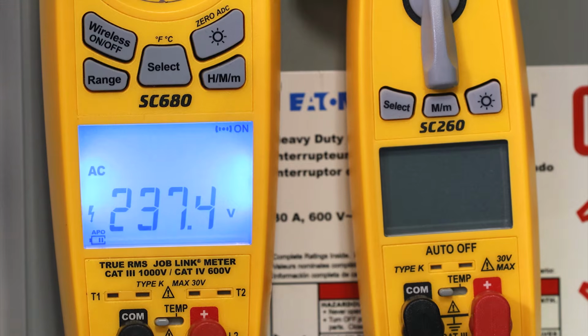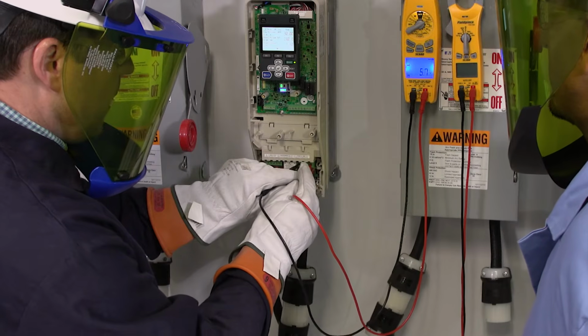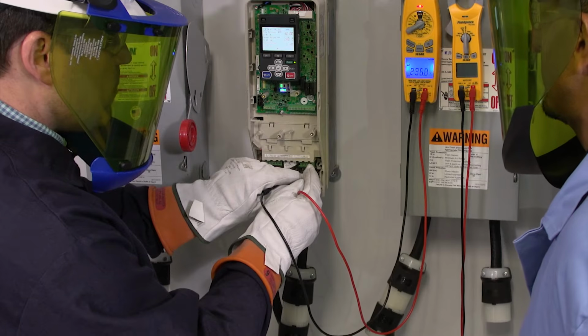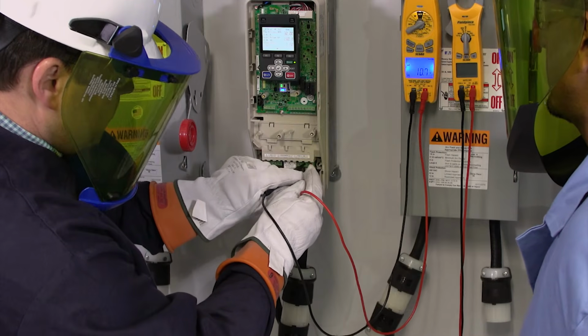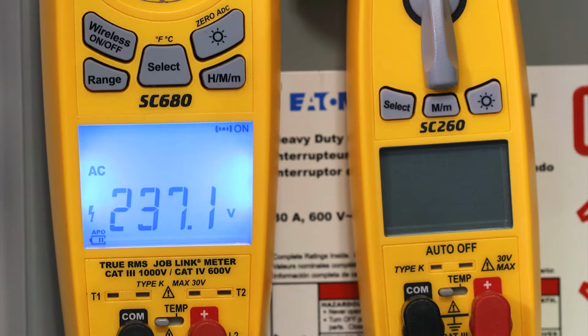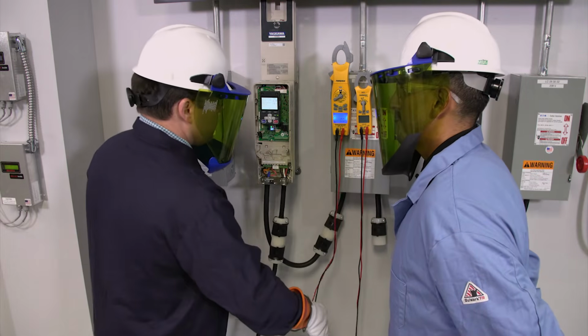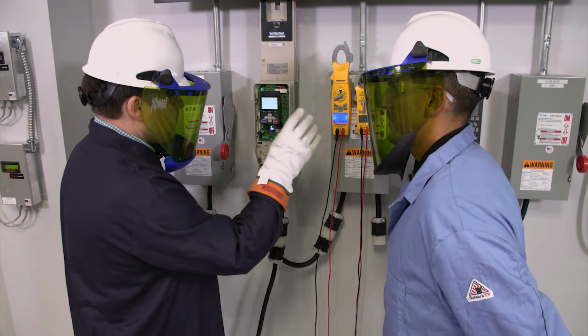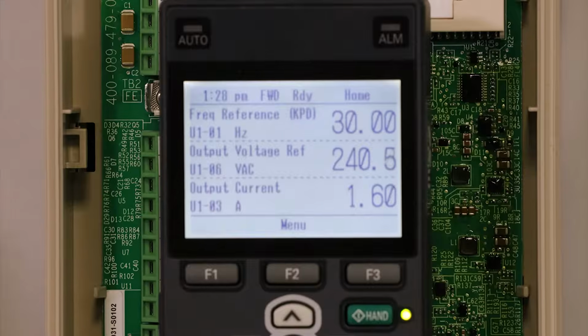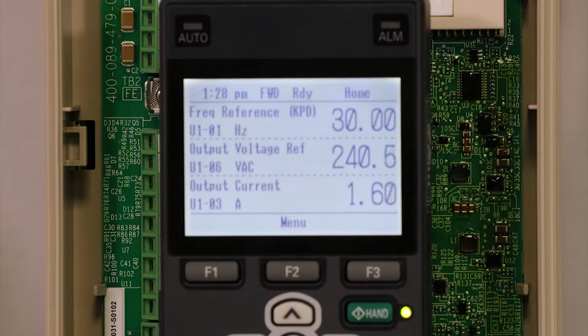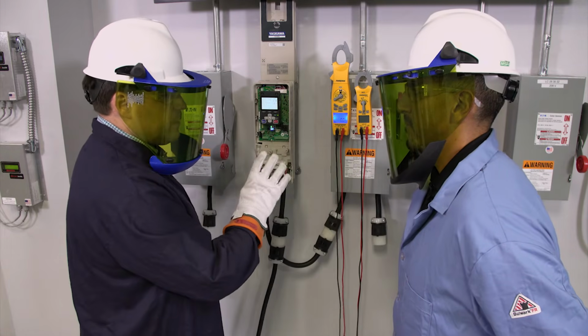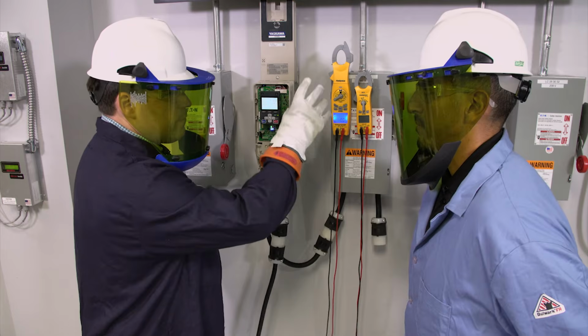You can see here we're at 237 volts, which is much less. 237 volts. 237 volts. Quite a bit of difference between those two readings. We know the filtered measurement is a lot closer to reality because the VFD's output voltage is approximately 240 volts. This proves that in these applications, we definitely need that filtered measurement.